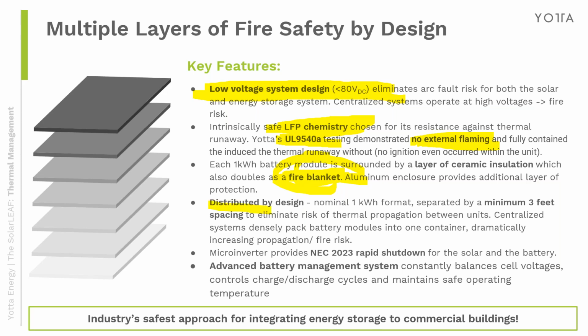The other nice thing is distributed by design. These are distributed on the roof, one under each module. Modules today are quite large, which gives us 3 feet or more of space between all the devices, so we don't need any kind of fire mitigation system on the roof. No fire suppression required. Rapid shutdown requirements, of course, are still valid here.